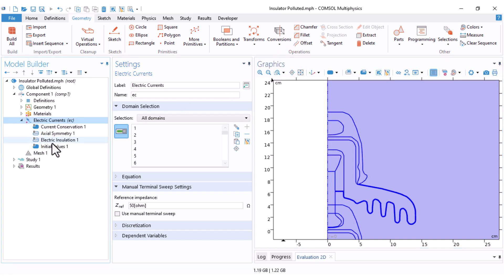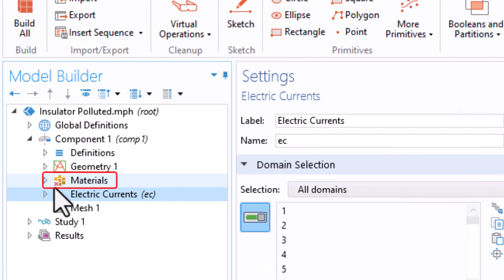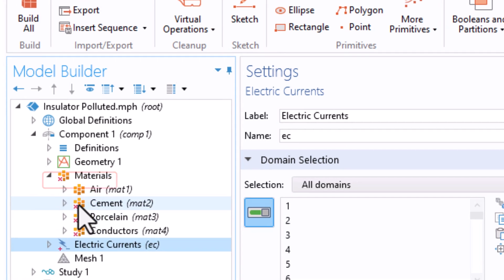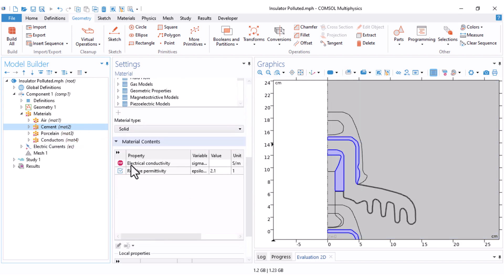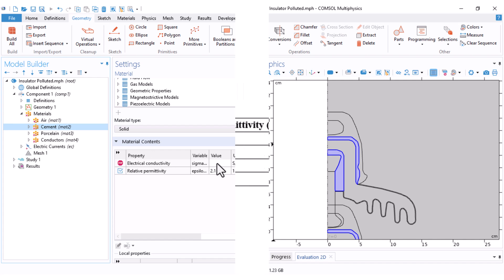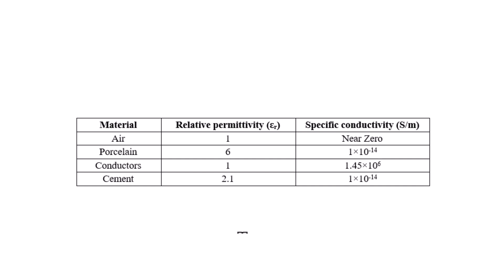A red cross has appeared on the Materials icon — it means some materials are missing specific parameters. Clicking on it shows that electric conductivity has been added as a required property and has not been defined yet. I now set the specific conductivity for each material. Porcelain and cement are set to 10 to the power of minus 14 S/m, and the conductors are set to 1.45 times 10 to the power of 6 S/m.